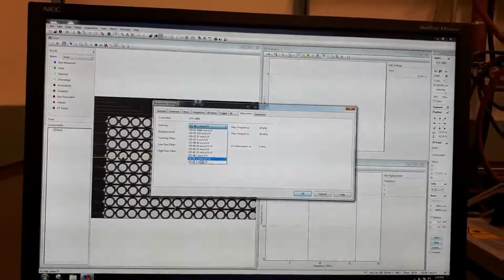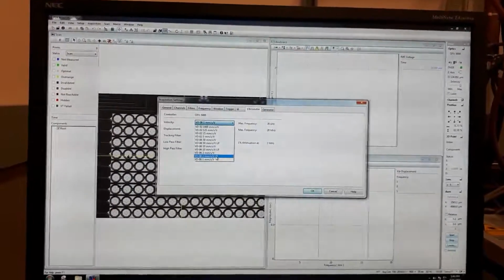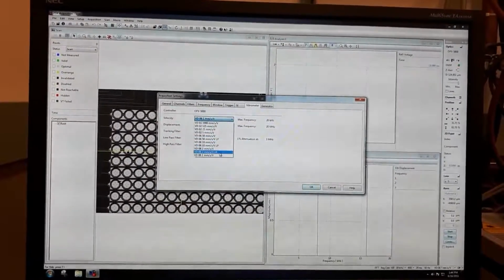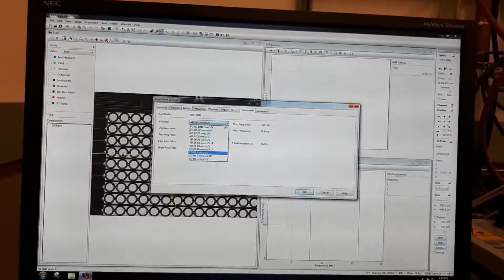So we only have two decoders, but with multiple subdivisions on each one. The main difference is the frequency range you can detect with each one. For instance, VD01, 1 millimeter per second per volt, gives you up to 20 kilohertz. The next one goes up to 100 kilohertz. The third one goes to 350, and so on and so forth.